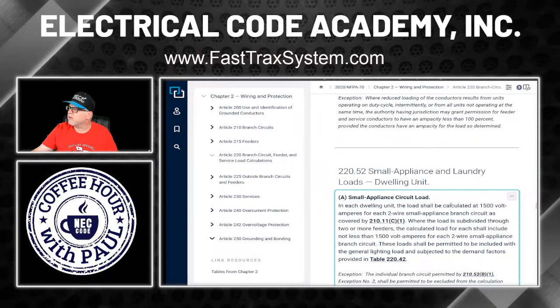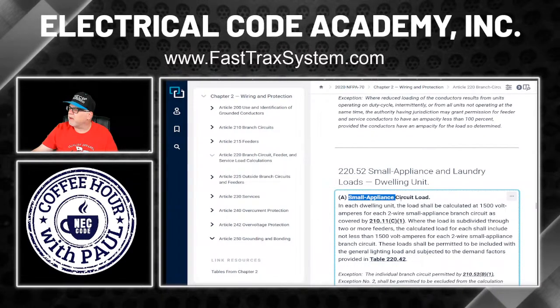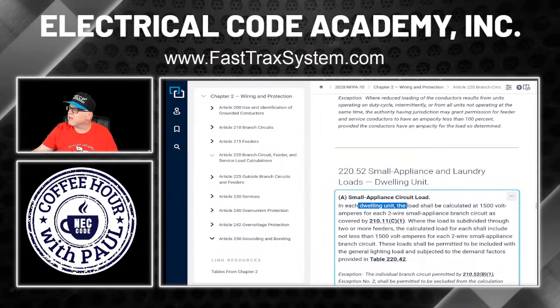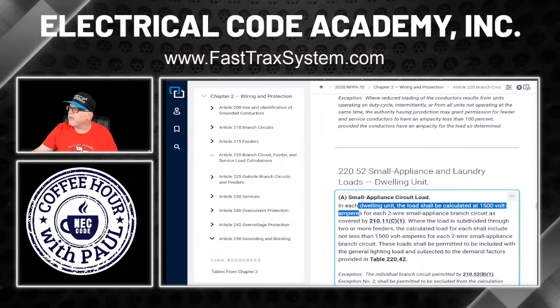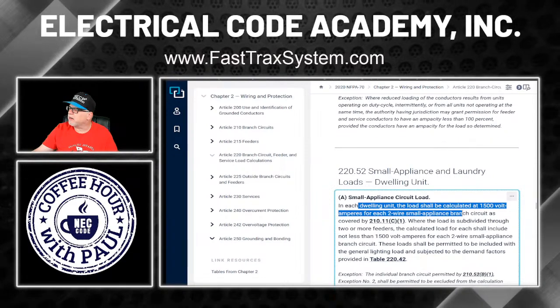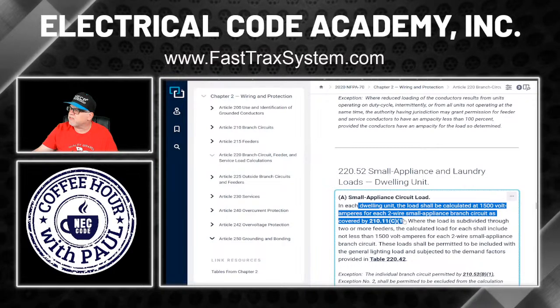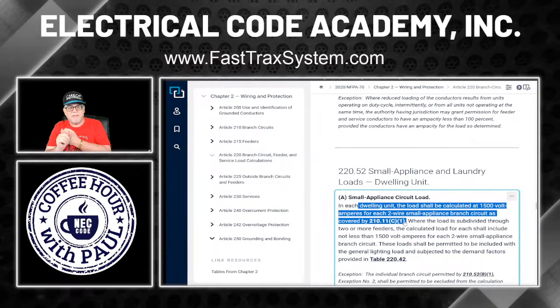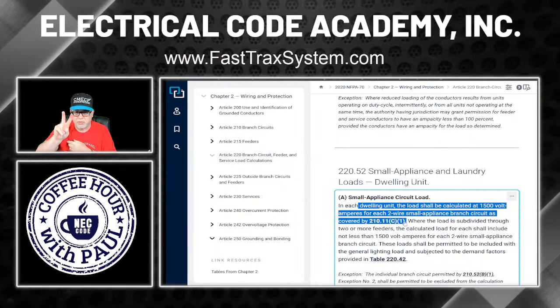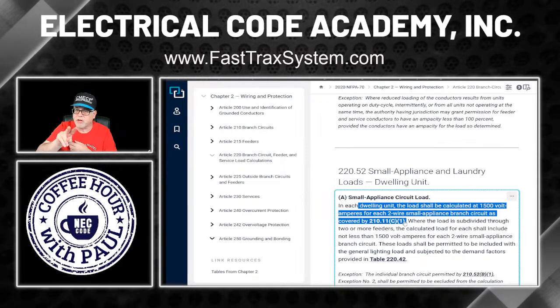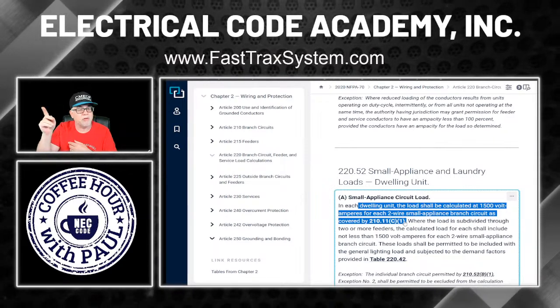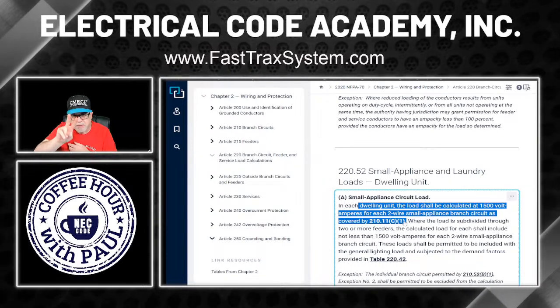So in this case, here we see what it says. Each dwelling unit, for the small appliance, the load shall be calculated at 1500 VA for each 2-wire small appliance branch circuit covered in 210.11(C)(1). Of course, if you know 210.11(C)(1), that's the one that requires a minimum of 2. That's in branch circuit, it tells you the number. You've got a minimum of 2. Could you have more than 2? Absolutely, but you have to have a minimum of 2.